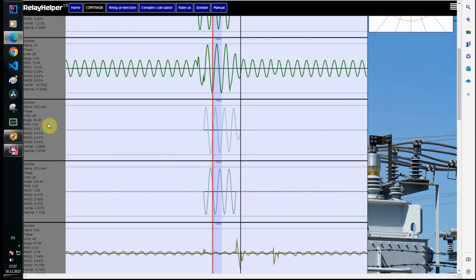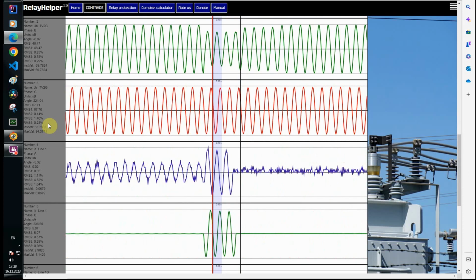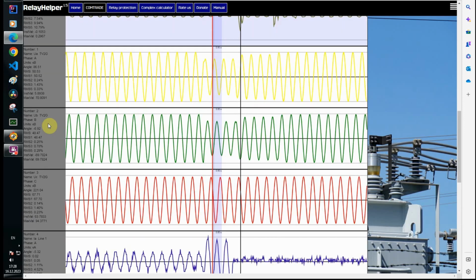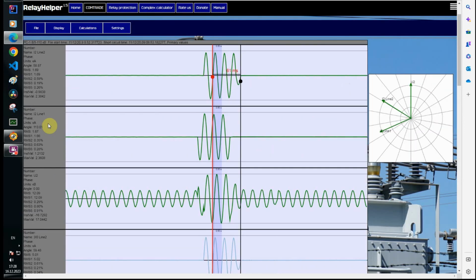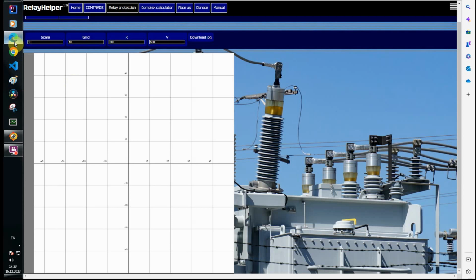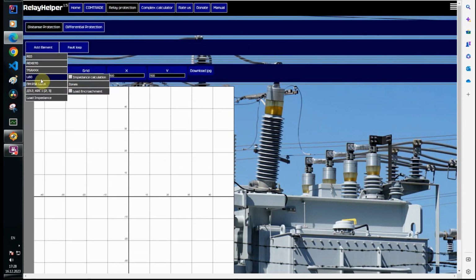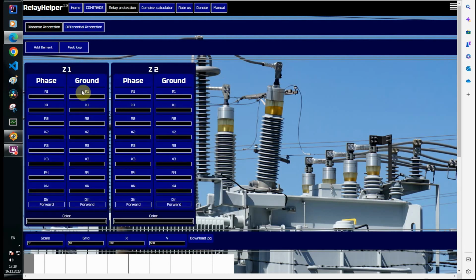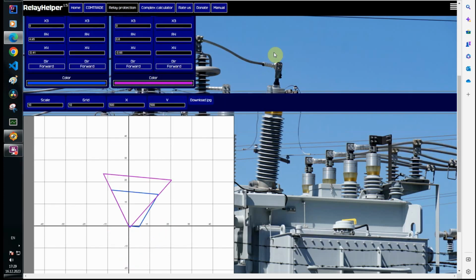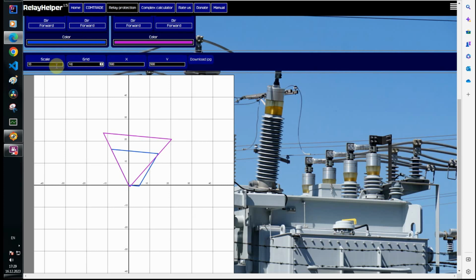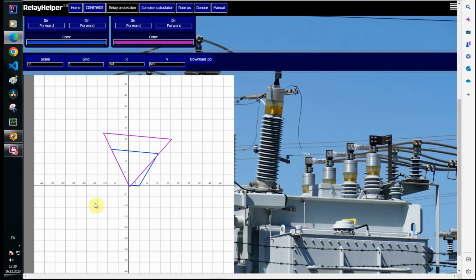It's still a mystery to me why the current increases only in one phase on each line. In theory, it should increase in both. Let's see how the devices saw what was happening. I'm adding 2 zones because this device doesn't have more. I enter the settings. The device uses only distance protection for phase-to-phase faults. It is easy to form a characteristic in IED. To do this, you just need to enter the coordinates of 4 points in the impedance plane, which will limit the characteristic of the zone.